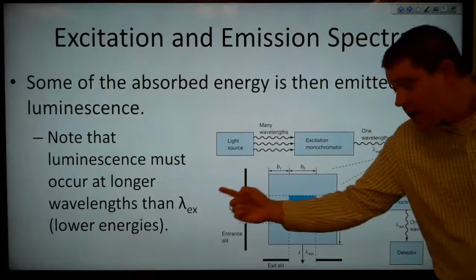Now that multi-wavelength emitted light leaves our sample via an exit slit, usually at a 90-degree angle with respect to the entrance slit, so the light is coming in here, and that light would go through. So we don't want to put our detector over there, because we would be detecting both the light from the source and the light from our sample. Instead, if we put our detector down here, we're only going to get light that is emitted from our sample. So this multi-wavelength light then goes into our emission monochromator, which selects one wavelength to pass onto the detector.